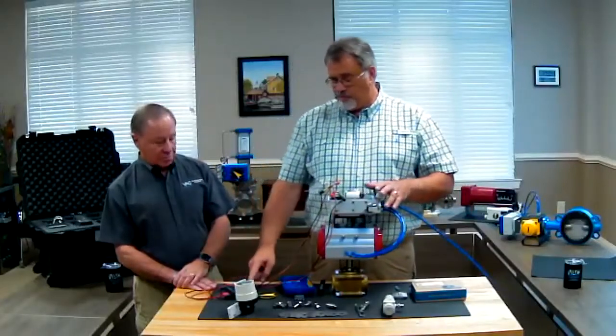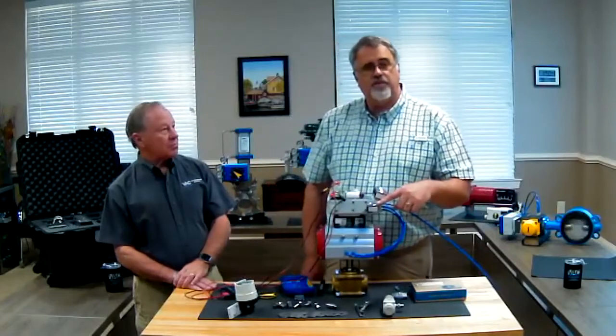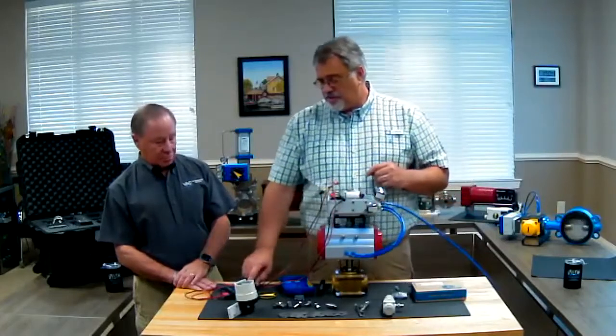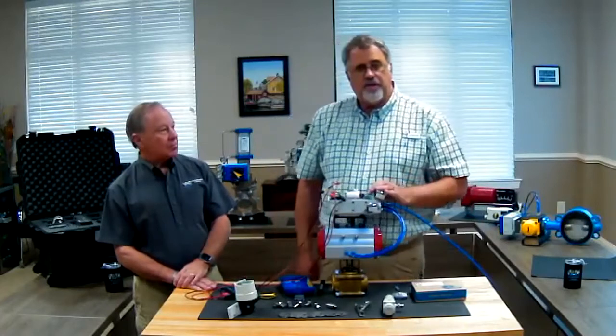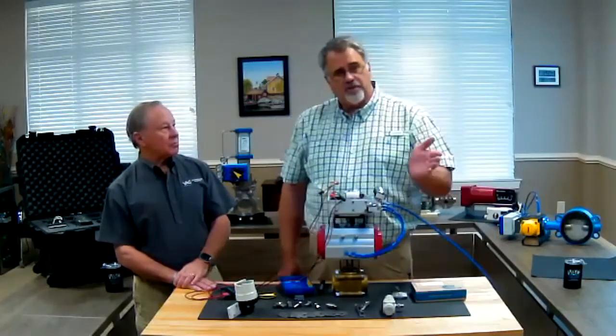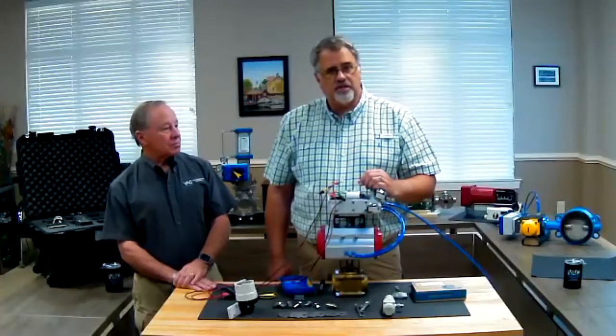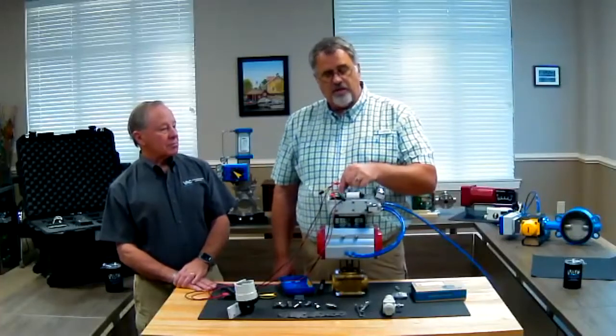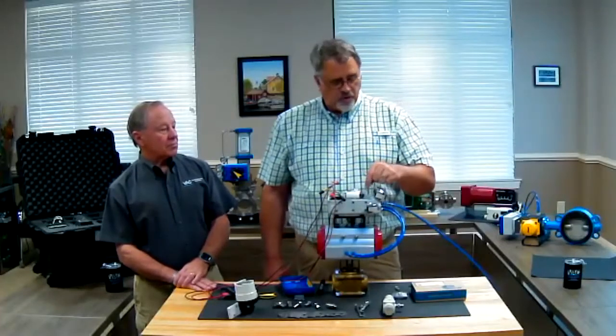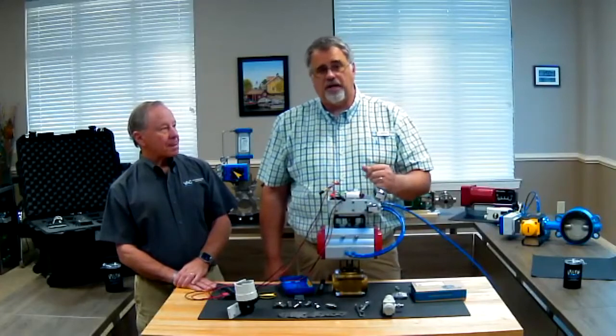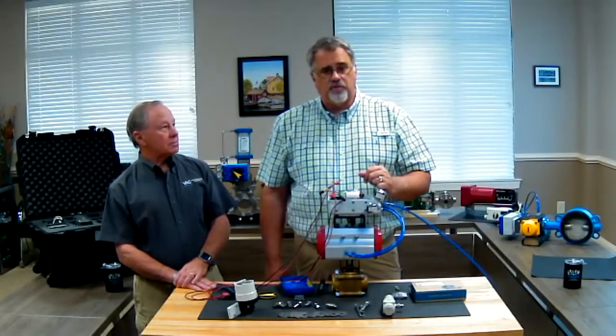But if I put 4 milliamps on my I to P, this gauge should read 3 PSI. At 20 milliamps, it should read 15 PSI. And this gauge should move smoothly between that 3 and 15 PSI when you make that signal change. If it does, then you know that the I to P is good, and the problem has to be in a pilot valve. Usually pilot valves can be cleaned rather than replaced.